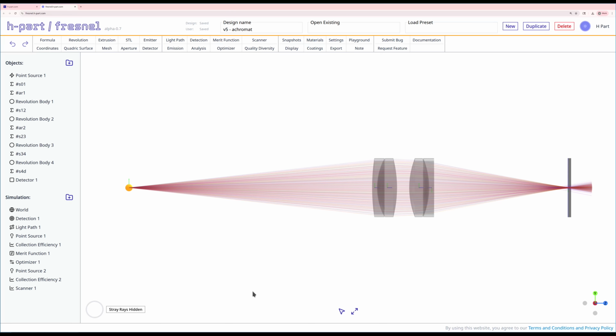We noticed that when we did that across a broad range of wavelengths, we suffered heavily due to chromatic aberration. We addressed that problem by designing 2 achromats that corrected for the chromatic aberration and gave us much higher collection efficiency overall, but remarkably better collection efficiency in the ultraviolet range.